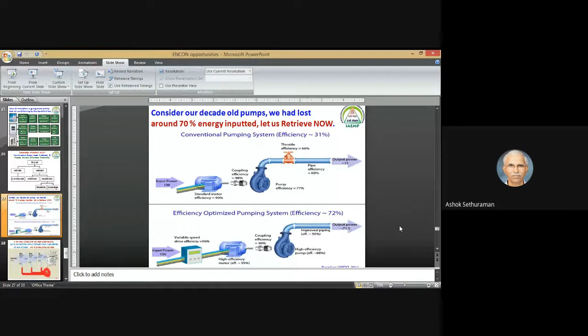For piping, Indian agriculture has moved to rigid PVC pipes in many places, but industries still haven't changed - industries still use MS/GI pipes and cast iron or ductile pipes, where the frictional loss is more. So moving from existing MS or GI pipes to rigid PVC pipes can be done in your college or in your house. You can see 20% energy savings is possible just by replacing the piping for a given pumping application.